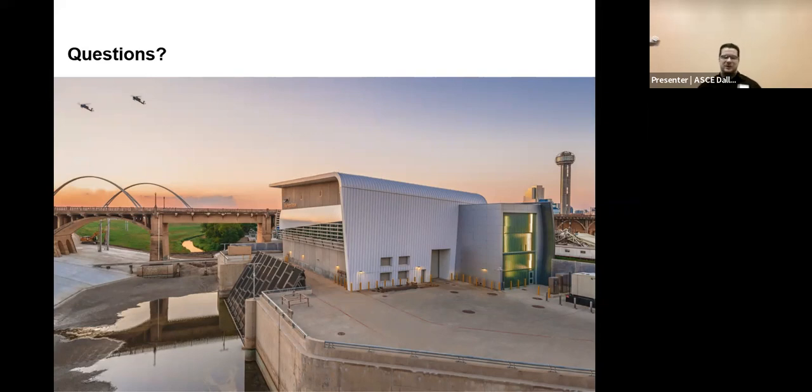Yeah, and speaking of water damage, it reminds me of the water-cooled VFDs inside, where the pipes constantly break, so you have water getting into everything electrical. Well, I think you just commented on my question. I was going to ask if these were constant speed or if these pumps had VFDs on them. They're VFDs. But with that large a draw, starting straight, 4,000 horsepower motors would be too large, especially for the area and what the electrical feeds can provide.